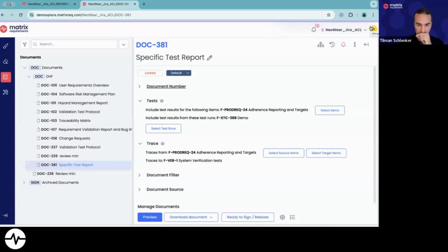So if you realize after one increment that maybe a validity check you have in your software doesn't work as intended, then you need to go back to the requirements and the specification, and update it there. And if you do that, you want to make sure that the tests actually cover this new functionality. This was just a very rough introduction. I'll get into more about the specifics for the testing, but for now, I'll give it back to Cyril.